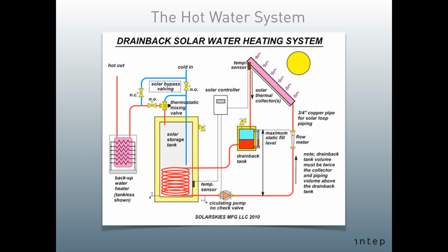It's a so-called drain back system. So when the tank is satisfied and there's still sun up, we don't need it anymore, and the panels simply empty themselves of the heat exchanger liquid and go idle. If there's another call for heat, the panels receive the liquid back again, come online, and start providing heat for the storage tank.